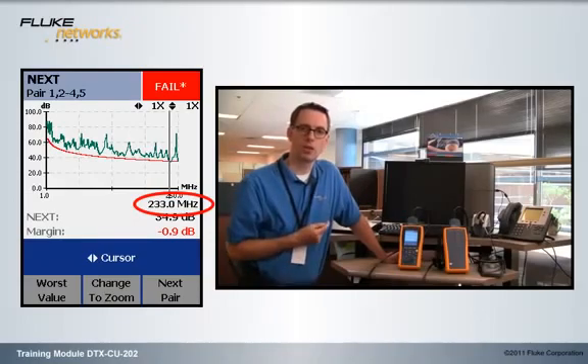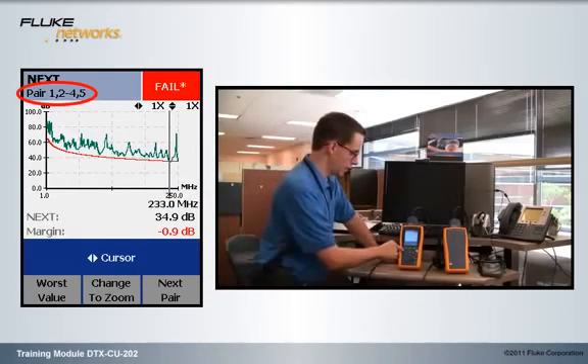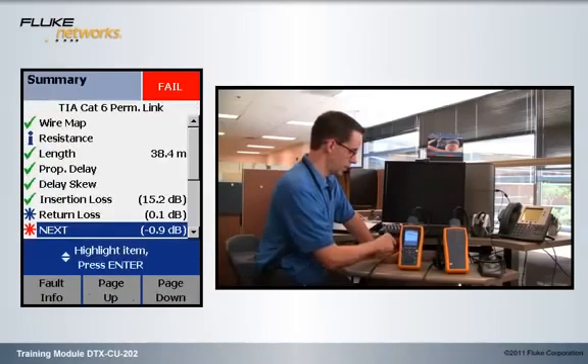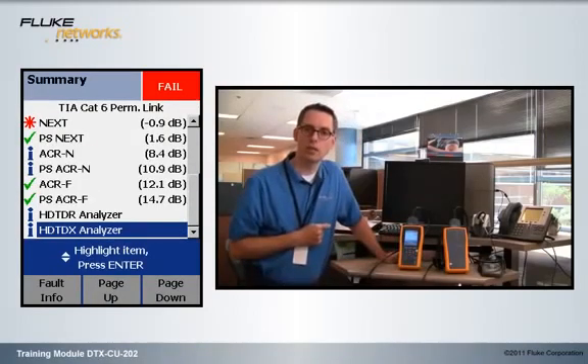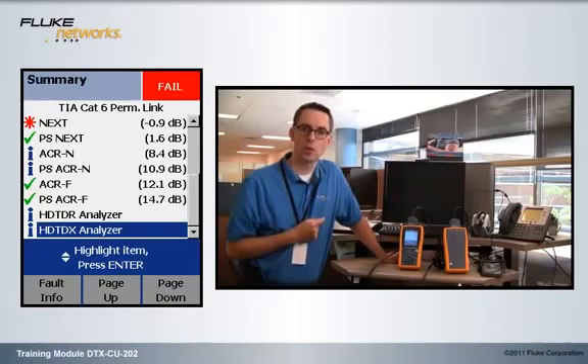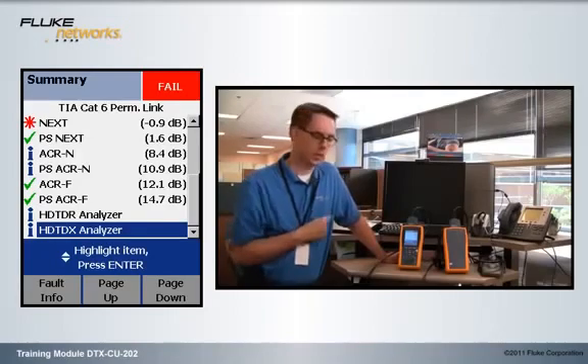Alright, so we know it's 1, 2, 4, 5. Next step, hit the exit key, exit key and page down to something called HDTDX Analyzer. This is that tool I was talking about in previous modules that allows you to look down the cable and see where the crosstalk is happening.